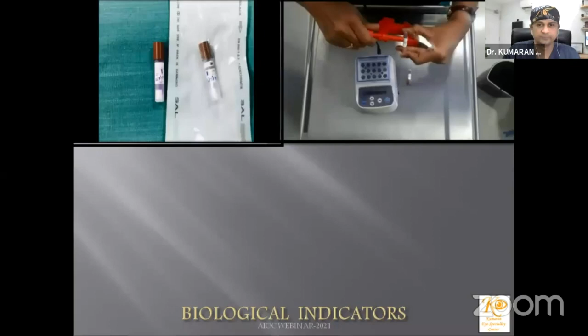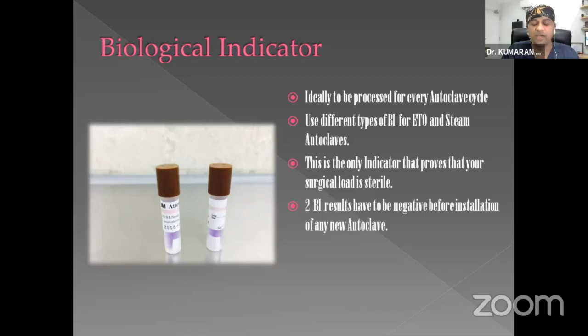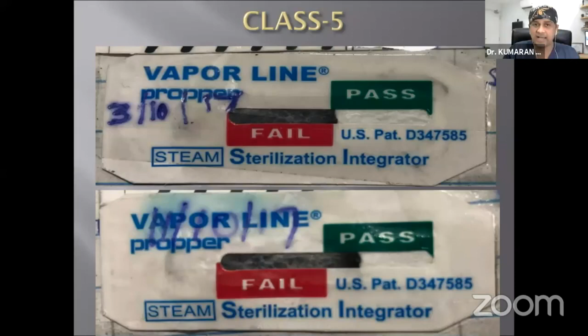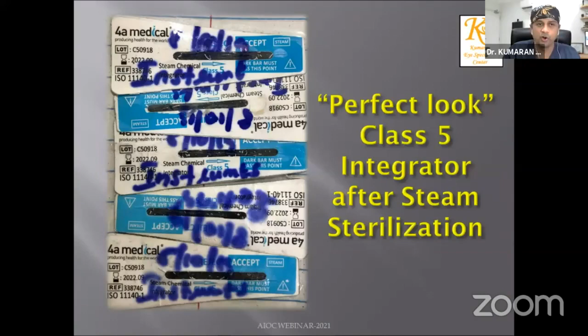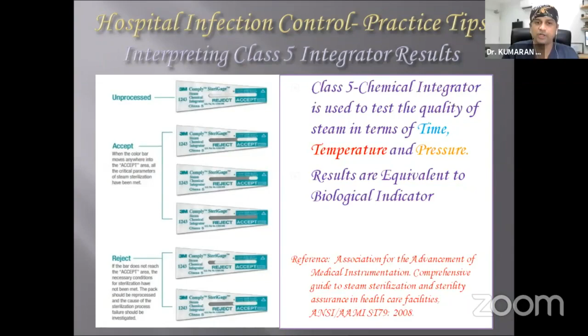So there are separate biological indicators for ETO and steam sterilization. Before you induct a new autoclave into installation, make sure that you have 2 biological indicators which have to be negative before you start using your autoclave. A class 5 autoclave indicator is equivalent to a biological indicator. And this is a perfect look of a class 5 integrator. These are the manufacturer guidelines which show what is negative and what is positive for a class 5 integrator. Please follow this and make sure that you read it every time before you start your surgery.